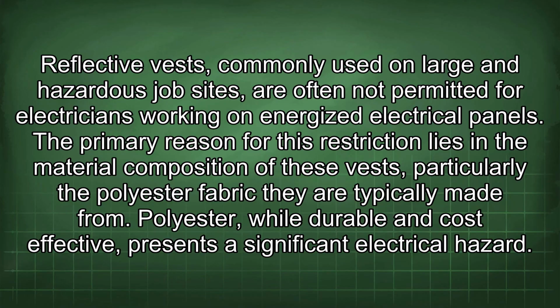Reflective vests, commonly used on large and hazardous job sites, are often not permitted for electricians working on energized electrical panels. The primary reason for this restriction lies in the material composition of these vests, particularly the polyester fabric they are typically made from. Polyester, while durable and cost-effective, presents a significant electrical hazard.